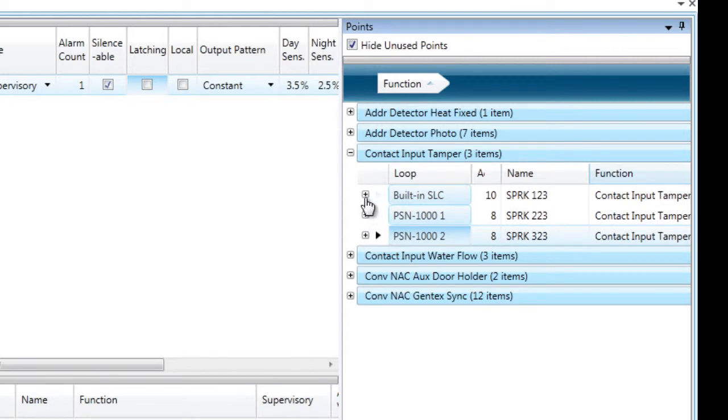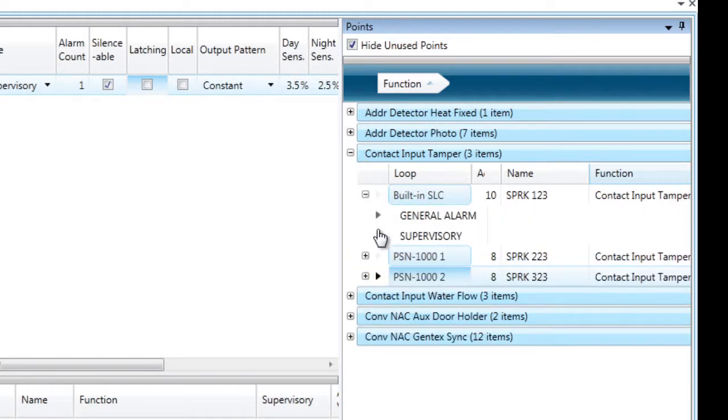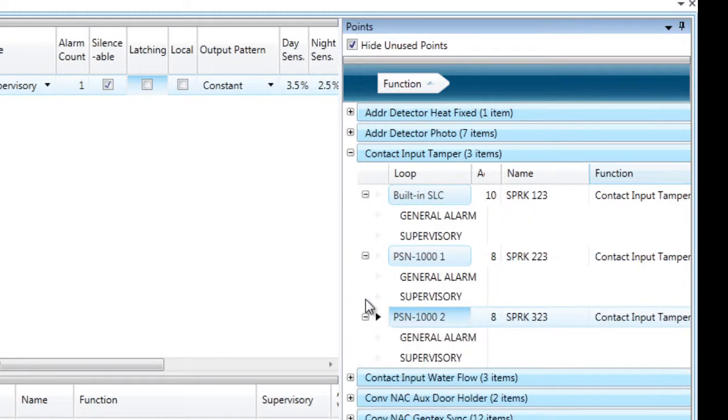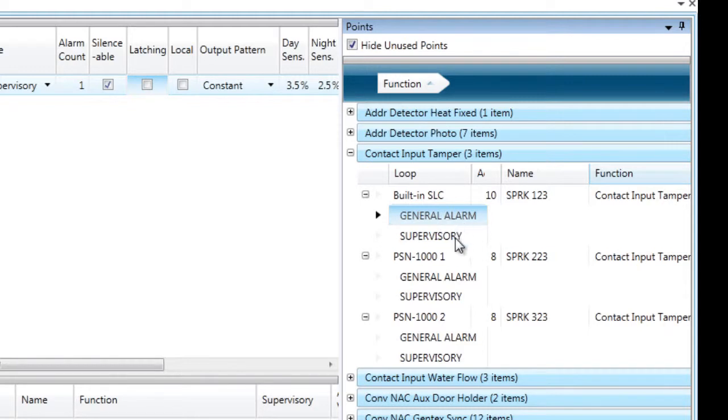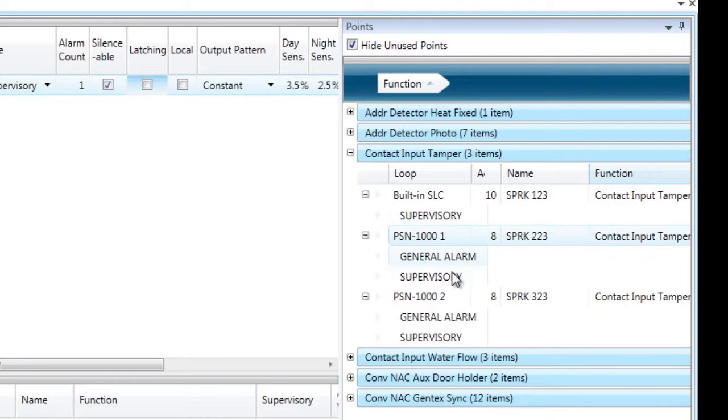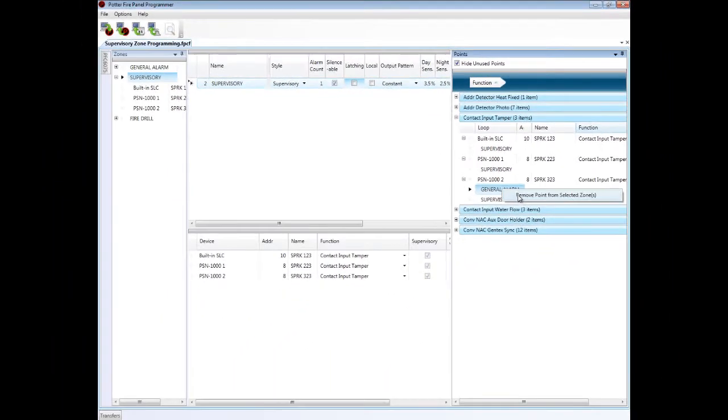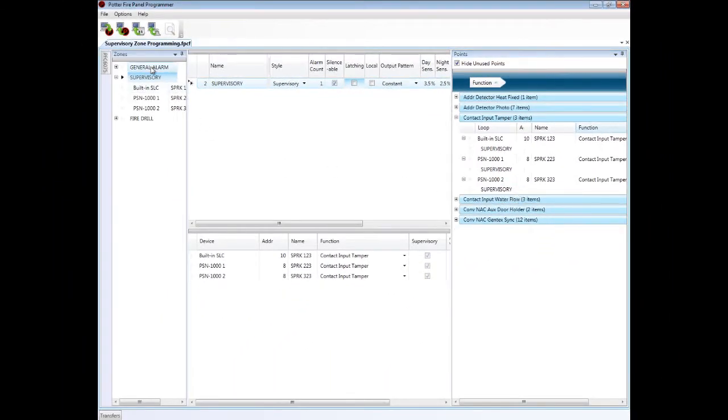Now, again, these are automatically in the alarm zone because when I did a learn, they came in by default as contact input tamper, and I have not removed them from the general alarm zone. So I can do so from the points list by selecting general alarm, left-clicking on that, and then right-clicking and removing that point from the zone. I can also have gone to the general alarm zone and found them and removed them that way as well.